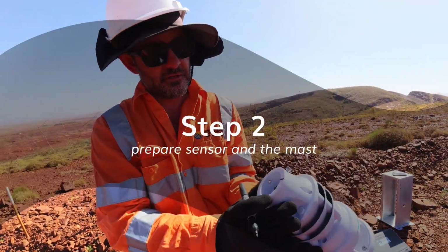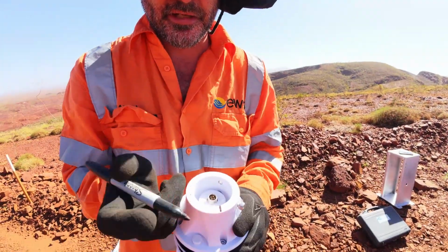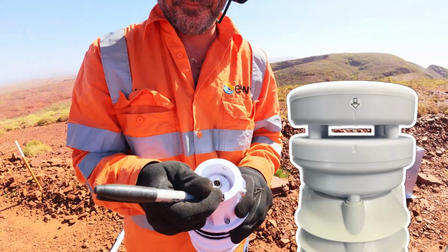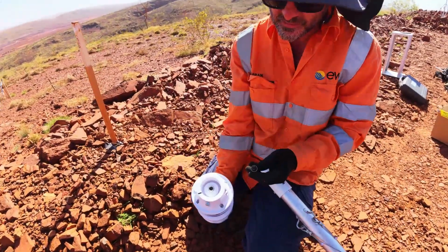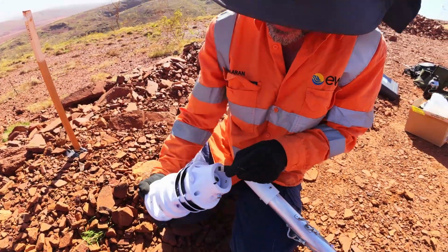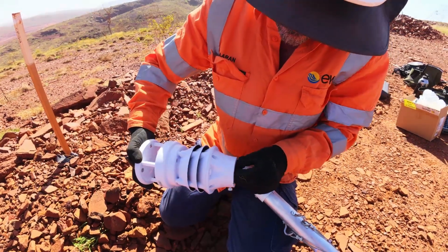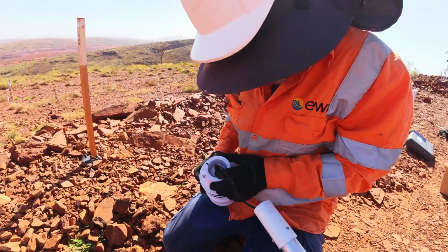Before raising the mast, locate the north direction marker on the sensor unit. Mark the north line clearly on the sensor's base with the intention of being visible from below. Plug in the sensor cable at the base of the weather sensor, then slide the sensor onto the mast.